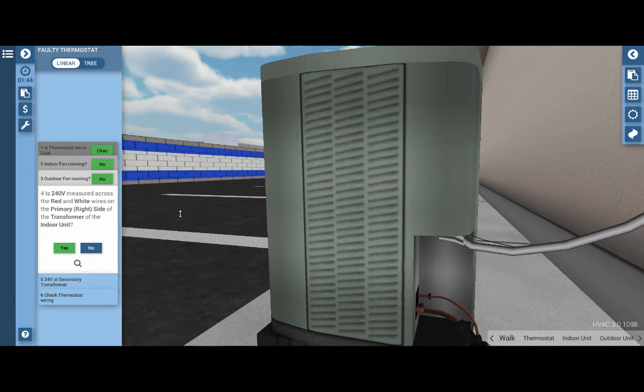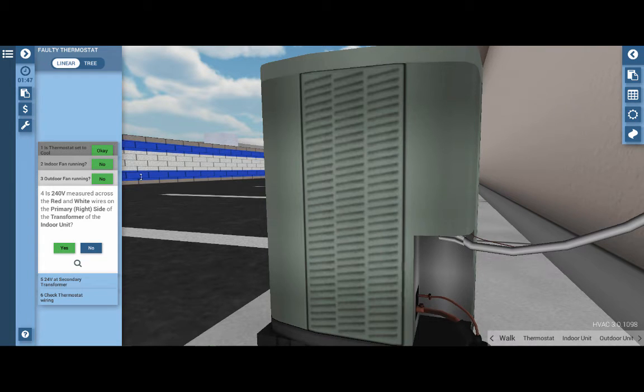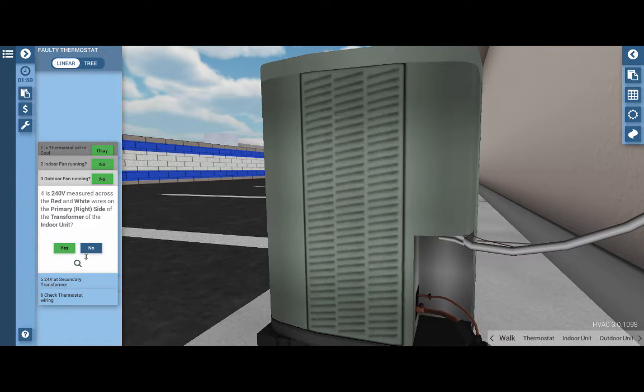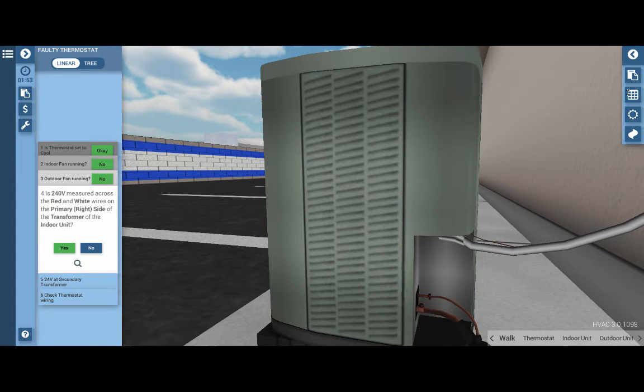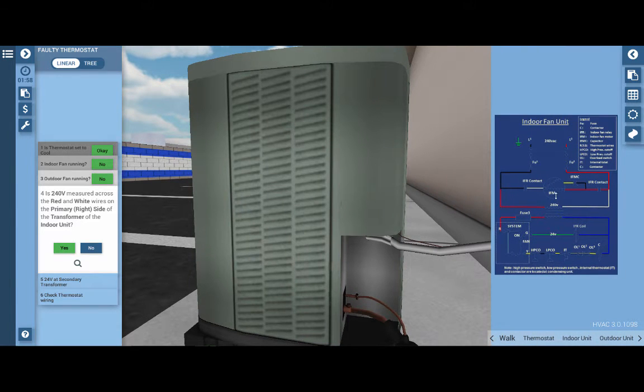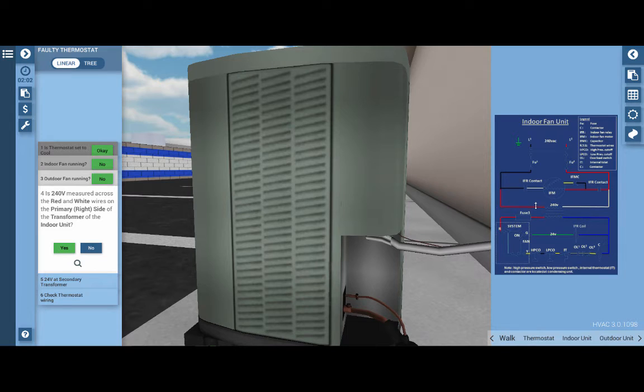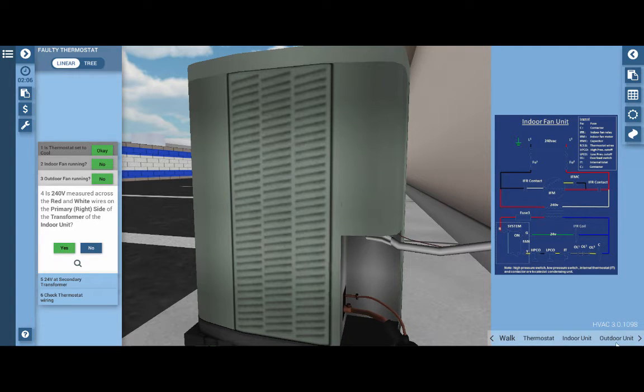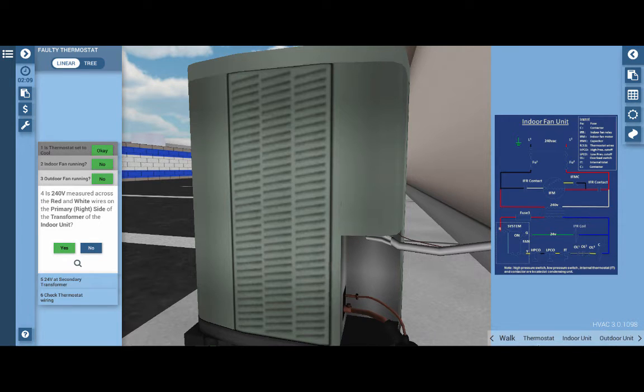Next, we want to measure for 240 volts across the red and white wires on the primary side of the transformer at the indoor unit. Before I do this, I'm going to take out the electrical wiring diagram up here on the top right tab, which will help guide us through this troubleshooting procedure. So our first step is just seeing if, in fact, the transformer here is receiving power.